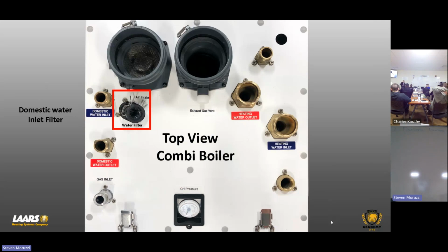Hypothetically, if you wanted to pull that, you're going to have ball valves on your cold water feed anyways, right? And you isolate that, open up a fixture and relieve the pressure. Well, let's say that ball valve is, I don't know, 18 inches above the top of that heater. I still have water there. And if I pull that filter out, right, what happens? I'm going to get water down on the top of this cabinet. And everyone's going to be concerned you're going to get water down inside. Well, every one of these fittings are backed up with a gasket. So that's a watertight cabinet, okay?